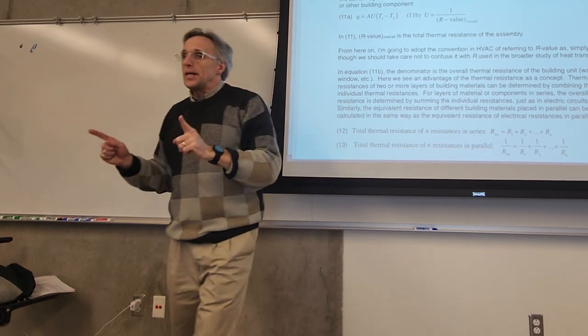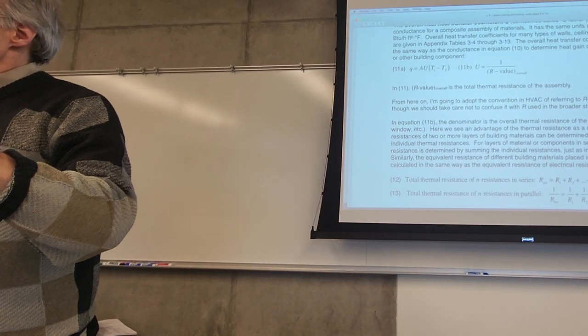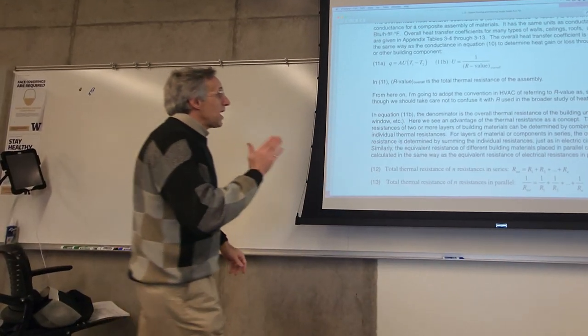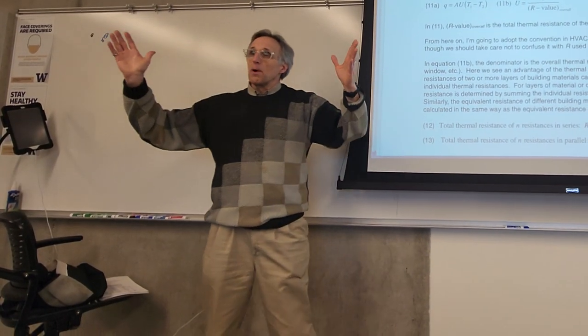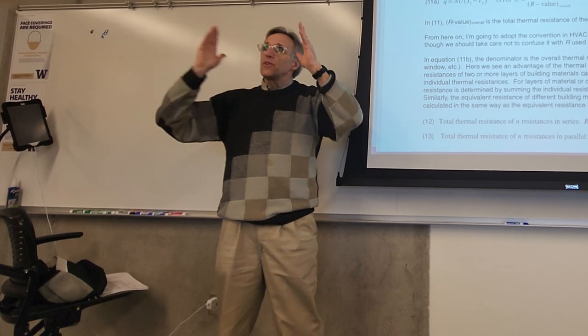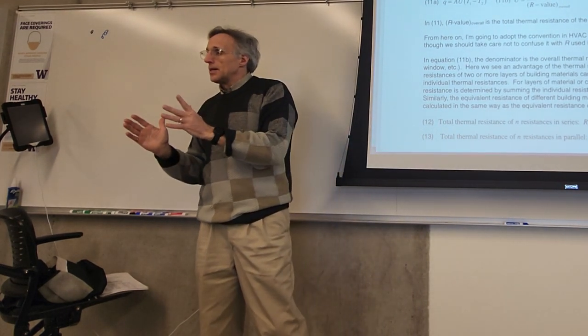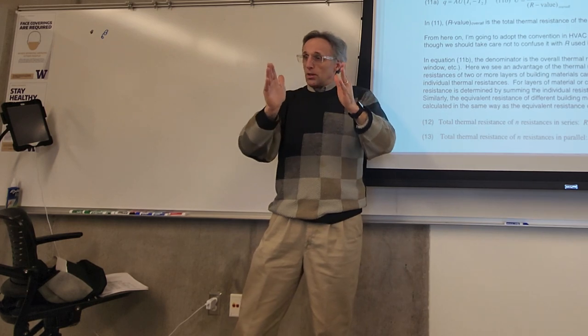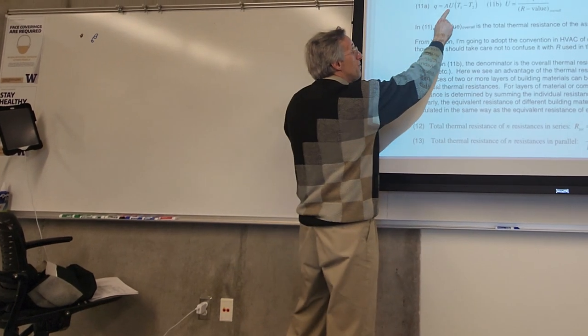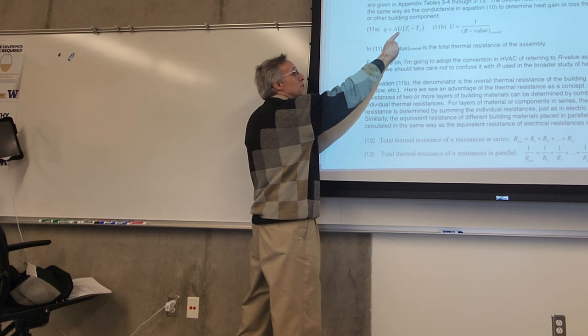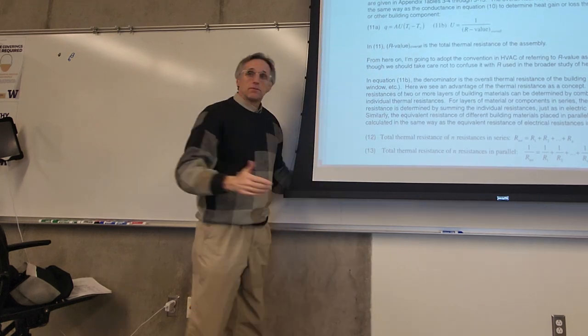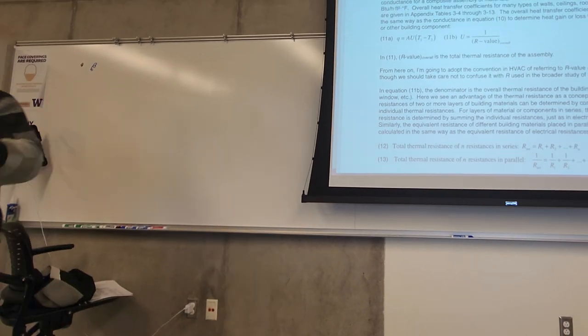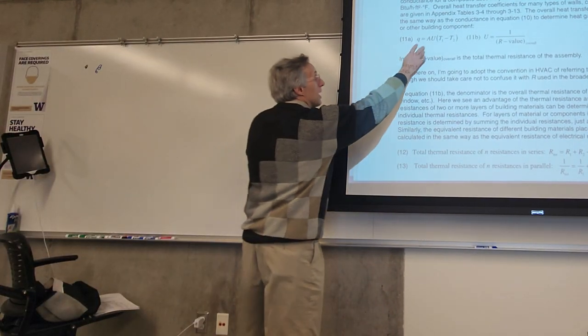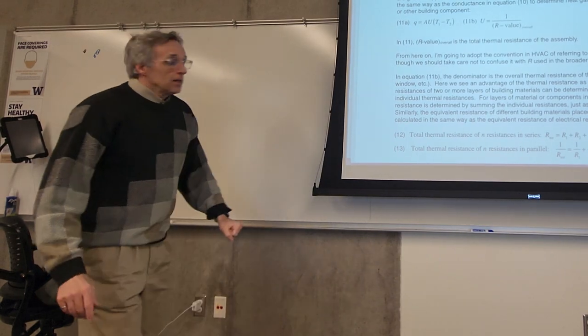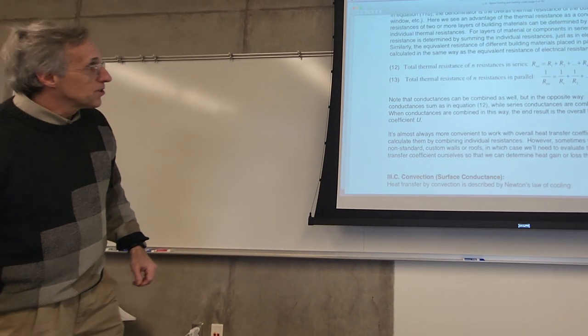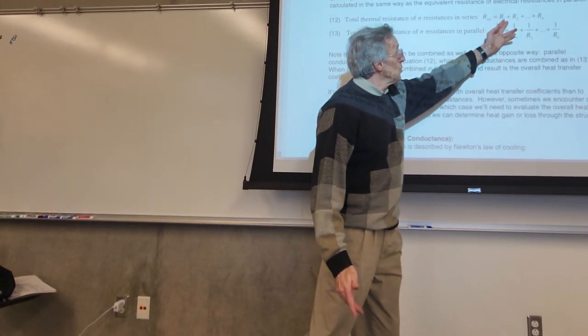And the nice thing about U is it's additive by area. And what I mean by that is, let's say my wall is 100 square feet. Let's say 50 square feet of that is window, and 50 square feet is wall. Then my U value is going to be 0.5 times U for the wall plus 0.5 times U for the window. And that gives me the U that I use to calculate the heat transfer. And so this is the total thermal resistance in series. We just add them up.